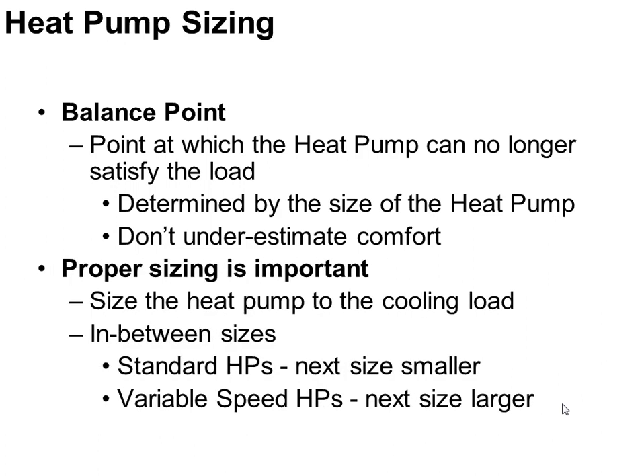Normally what we've done on heat pumps over the years is we size the heat pump for the cooling mode, right? And this is a pretty normal thing that we have to do. If we were to size the heat pump for the heating mode, we'd have like twice as big of a heat pump as we might want for cooling season, and it'd be a problem, right? So if I said, oh, your cooling load's 3 tons and your heating load is 6 tons worth of capacity, right? So 6 tons would be 72,000 BTUs, which is a pretty normal size house, right?